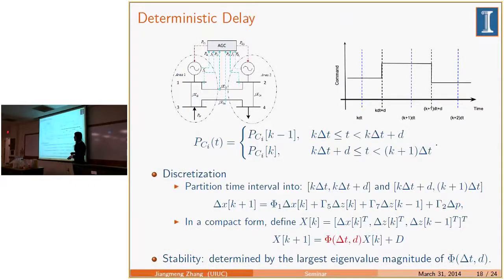If we consider measurement delays, it becomes a bit more complicated. Again, this is the AGC system - at the time when new measurements are taken, the new command has to wait for a time d until it arrives at the generator and takes effect. So there will be a time delay between when new measurements are taken and when the new command arrives at the generator and takes effect.